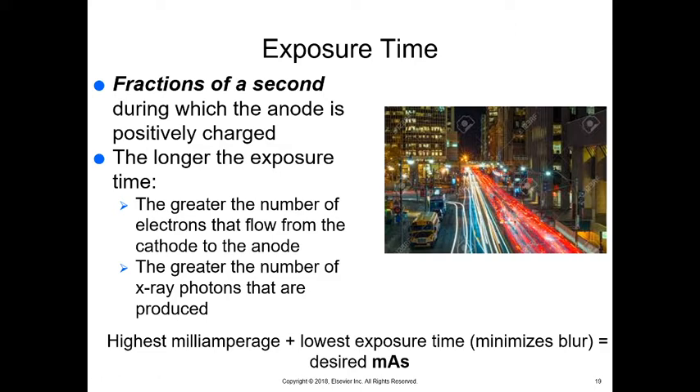Exposure time is fractions of a second — the time during which the anode is positively charged. The longer the exposure time, the greater the number of electrons flowing from cathode to anode. Think of a long-exposure photograph: things are blurry because you're opening the lens for a long period of time and can't see individual details. We want the highest milliamperage and the lowest exposure time to minimize blur, especially if the animal might be moving.